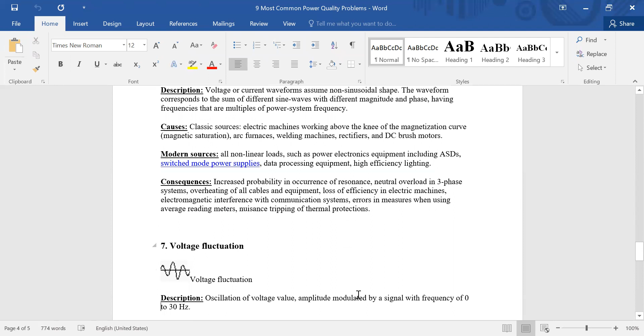So the voltage values will oscillate, amplitude modulated by a signal with the frequency 0 to 30 hertz. So that is the description for the voltage fluctuation. When we are talking about the causes of voltage fluctuation, the causes are arc furnaces, frequent start or stop of electrical motors, for instance elevators, and oscillating loads can also be a cause of voltage fluctuation.